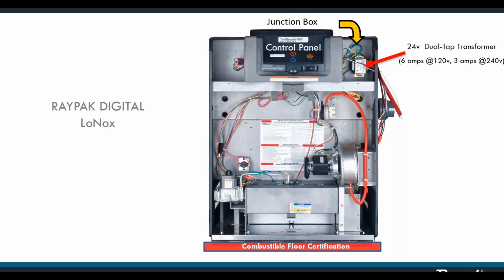Up top on the right, you'll notice a dual tap 24-volt transformer. That's inside of a junction box on the right there. This particular appliance pulls 6 amps at 120 volts or 3 amps at 240 volts. If that junction box is not appropriate for you, that is to say, if you want to pull the conduit up on the left instead of the right, there's an identical junction box on the left-hand side. You'll notice that it has pre-drilled holes in it. That's to mount your transformer if you should need to.